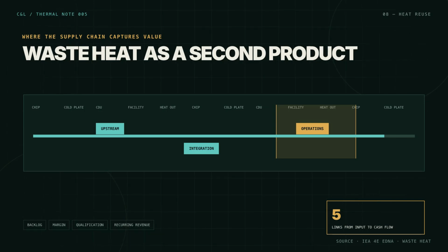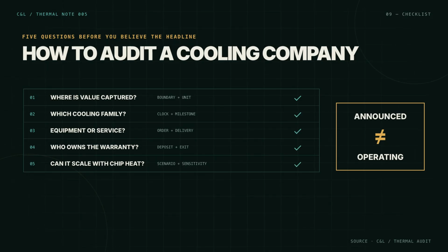Ask 5 questions. Where in the thermal chain does the company earn revenue? Is the product designed for direct-to-chip, immersion, rear door systems, or several? How much revenue is equipment, installation, consumables, and recurring service? Which customers have qualified the design, and who owns warranty risk across interfaces? Finally, what happens when chip power and rack density change? A cooling vendor can benefit from AI growth without touching a GPU, but only if it survives rapid standards, procurement cycles, and demanding uptime requirements. Revenue quality matters more than a slide showing total addressable market.